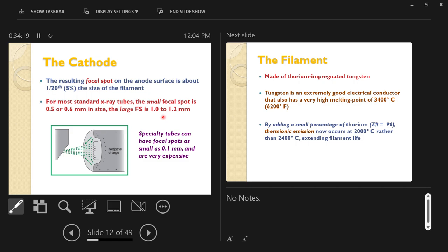Small focal spot: great detail, less capacity. Large focal spot: less detail, more capacity to carry electrons. If you want extreme detail — for example, angiographic radiography where you're imaging tiny blood vessels — you go to extremely small focal spots, like 0.1 millimeters. The disadvantage of a tiny focal spot is reduced x-ray output capacity.